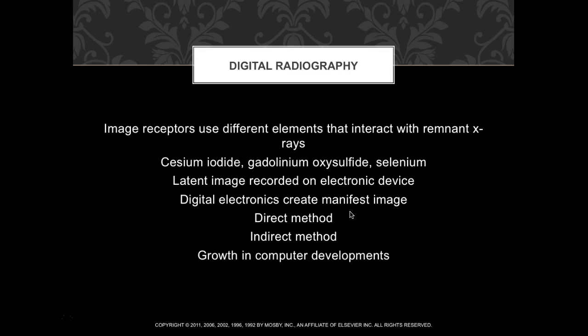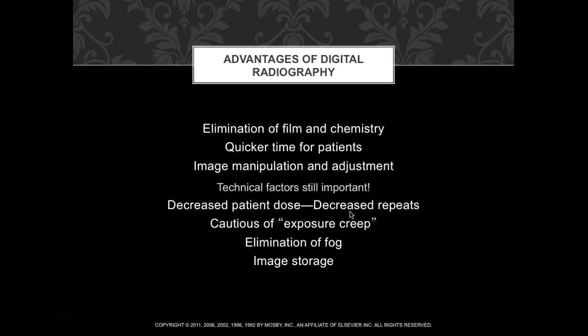Advantages of digital radiography include elimination of film and chemistry. With film-based systems, you had to monitor chemistry temperatures to avoid contamination, dryer issues causing sticky films, pressure marks if film wasn't stored upright, scratches, and static from low humidity causing unwanted exposure. Digital eliminates all of those problems.